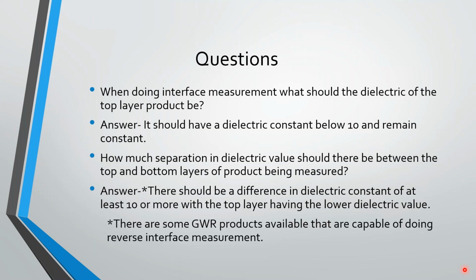There are some guided wave radar products available that are capable of doing reverse interface measurement - that's something to bear in mind. Not all guided wave radars can do this, but some devices can. In that case, if the lower dielectric is on the bottom and the higher dielectric is on top, which would be unusual but could happen with certain chemicals, devices that do reverse interface measurement will look at the slowdown in signal, similar to tank bottom following.